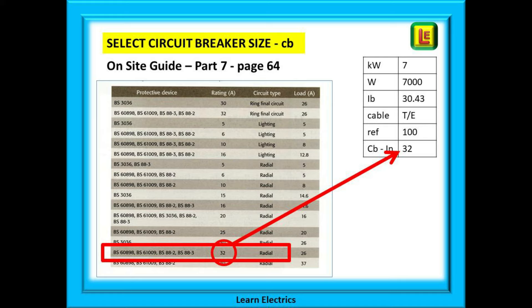This list shows the different types and sizes of fuses and breakers for different types of circuits — starting with ring circuits at the top, then lighting circuits, moving on to radial circuits. Towards the bottom for radial circuits we will find a BS EN 60898 breaker that is equal to or greater than 30.43 amps. In this case a 32 amp breaker. We can fill this in on our chart now: 32 amps.